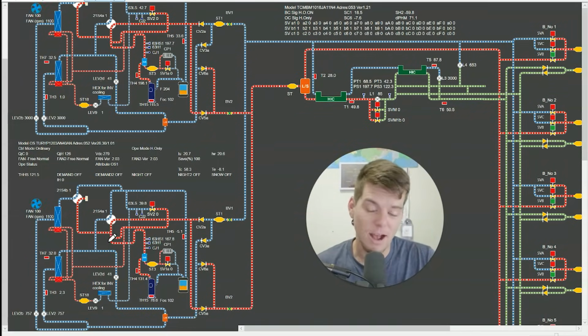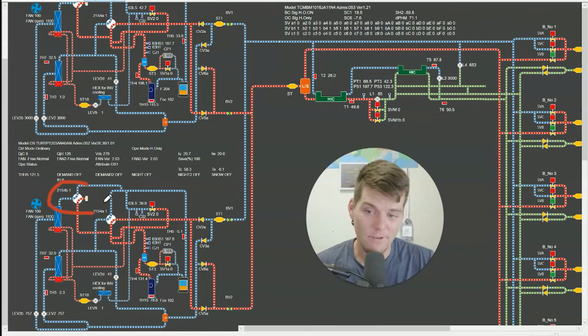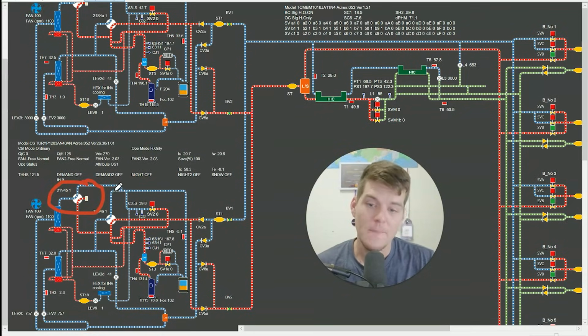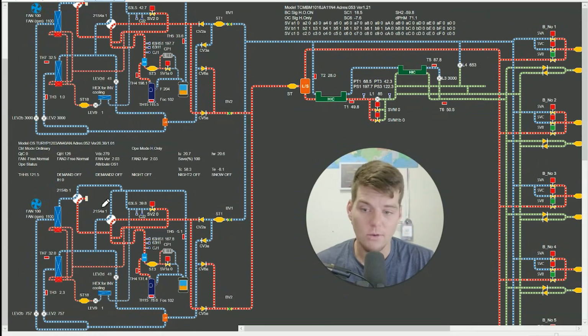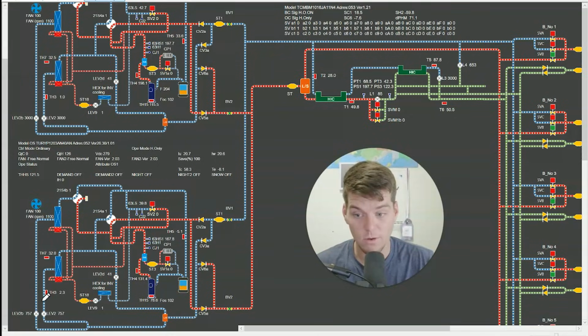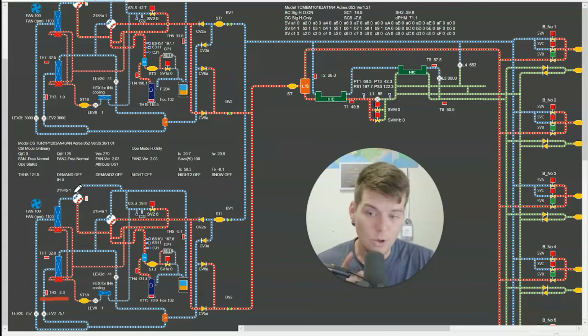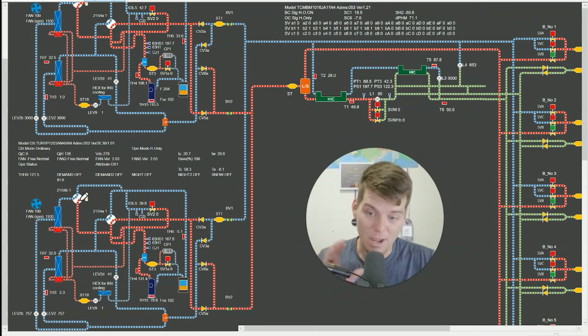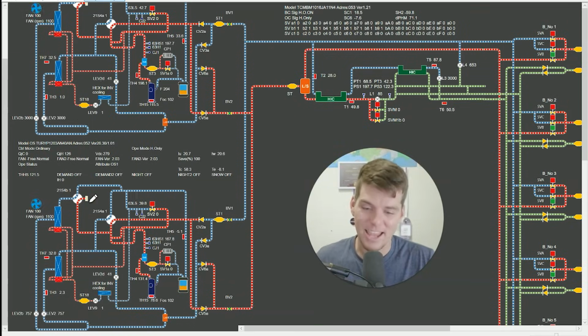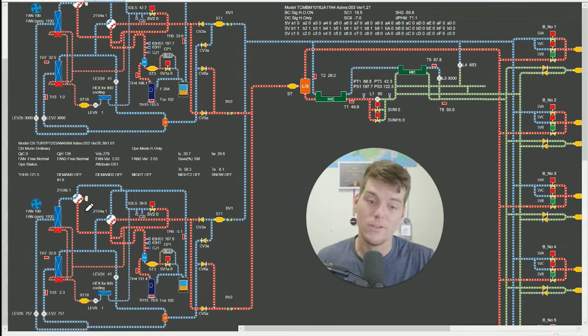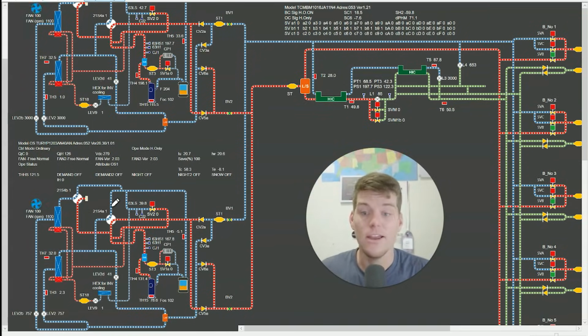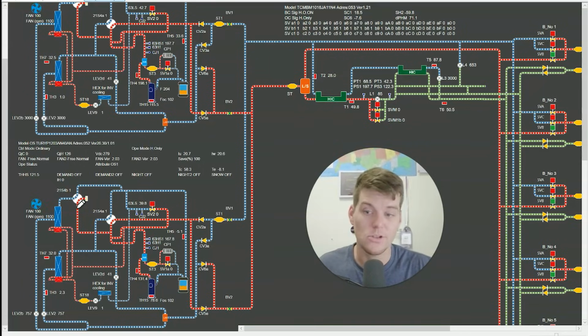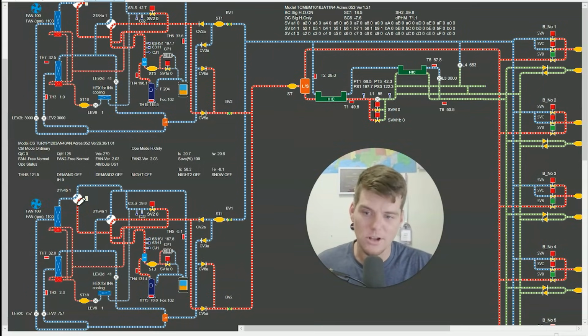Well, because in this module, this four-way valve has actually failed. And how do we know that? Well, because not only do we know that because, one, this temperature isn't at TC, but two, we had a technician go to site and I gave him the advice of checking that four-way valve, and lo and behold, he found it wrong. He found it not shifted the way it's supposed to. This four-way valve is stuck in cooling.